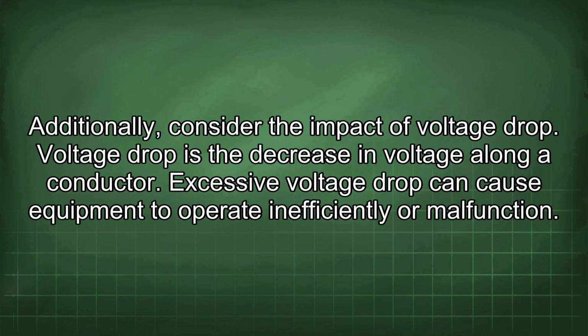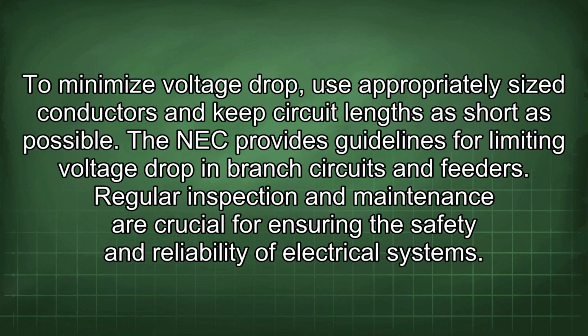Additionally, consider the impact of voltage drop. Voltage drop is the decrease in voltage along a conductor. Excessive voltage drop can cause equipment to operate inefficiently or malfunction. To minimize voltage drop, use appropriately sized conductors and keep circuit lengths as short as possible. The NEC provides guidelines for limiting voltage drop in branch circuits and feeders.